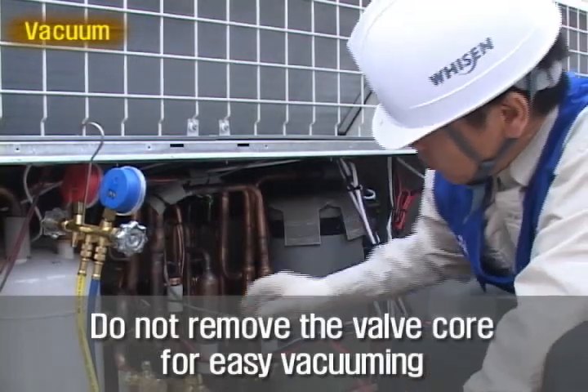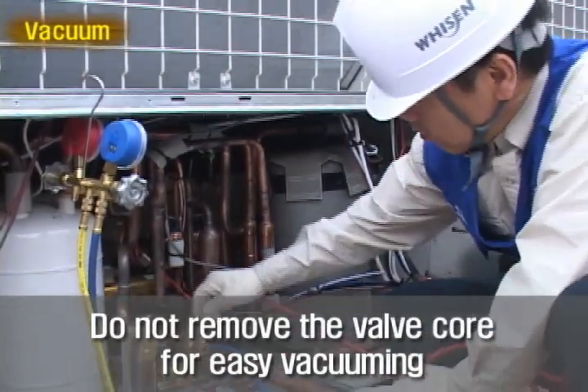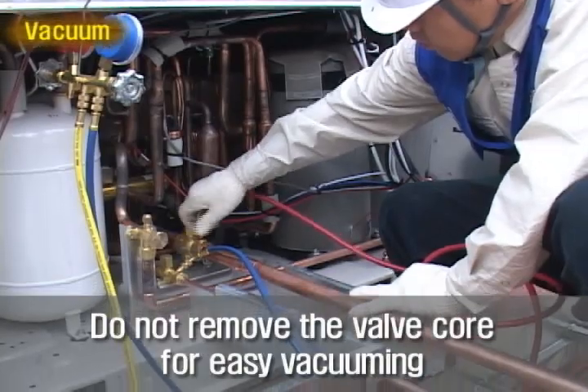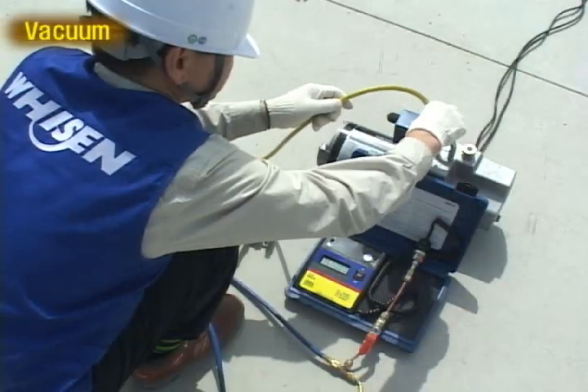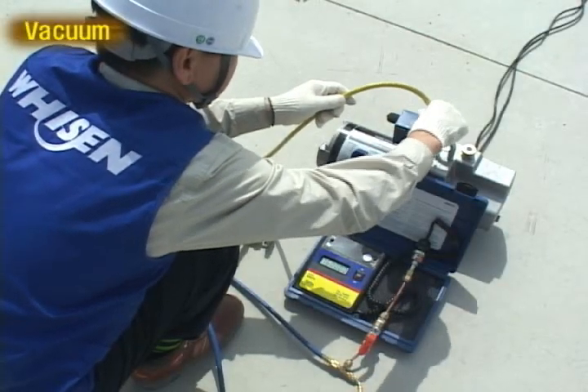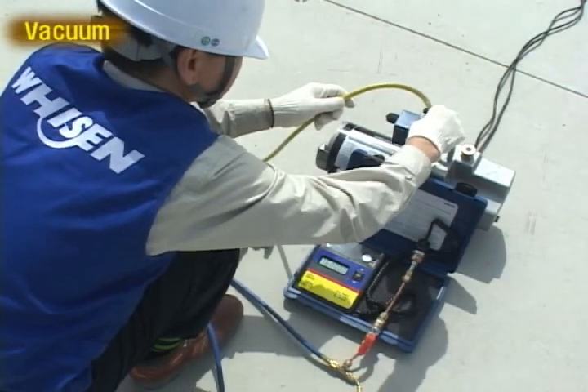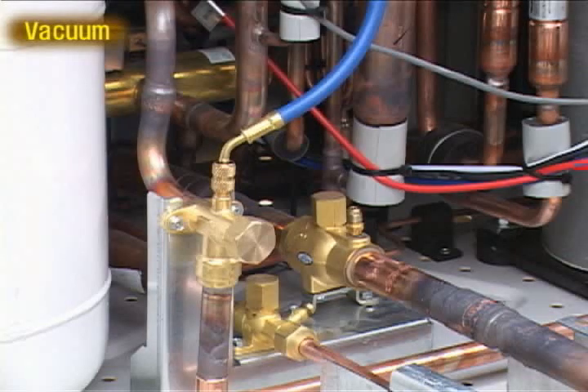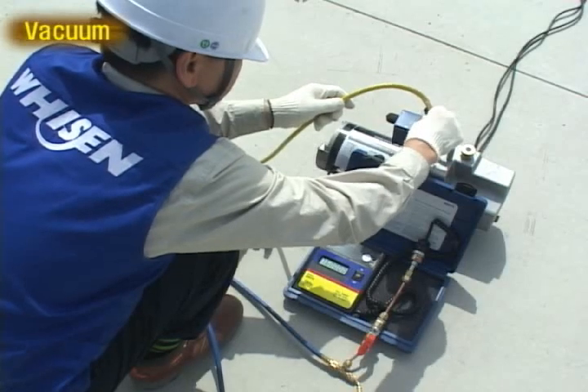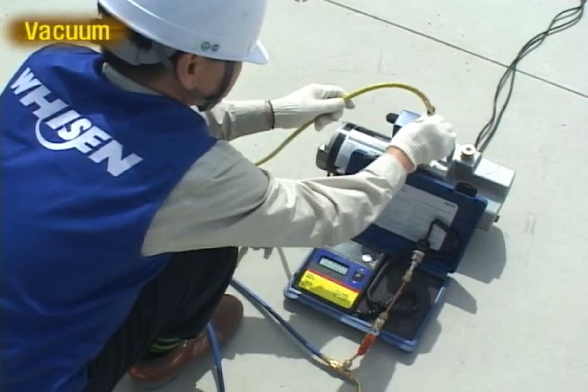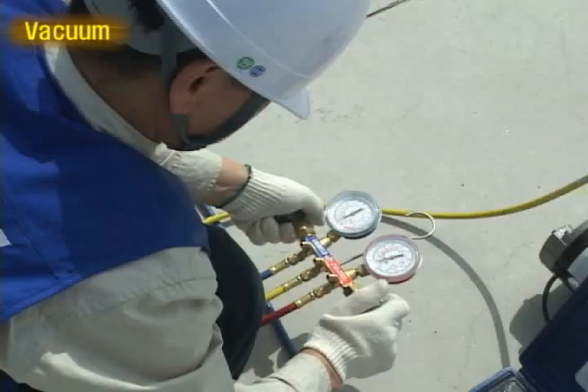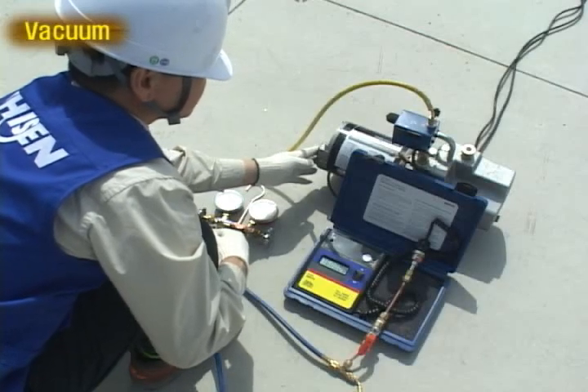For one outdoor unit model, vacuum after connecting the manifold gauge to the high and low pressure service valve and the common hose of the gauge to the pump. For 2 or more outdoor unit models, vacuum after connecting the sharing pipe additionally to the gauge. Confirm the high-low pressure valve of the manifold gauge is closed, and then start the vacuuming operation. Slowly open the low pressure valve of the manifold gauge.